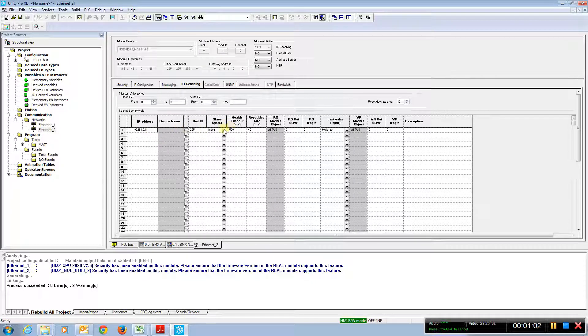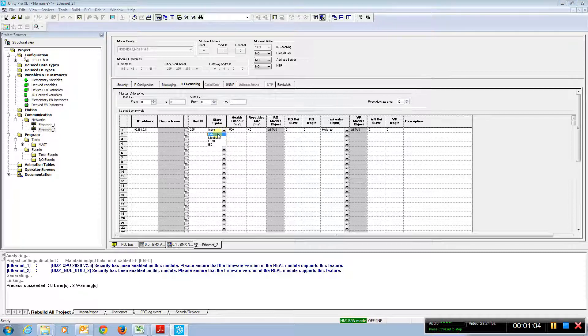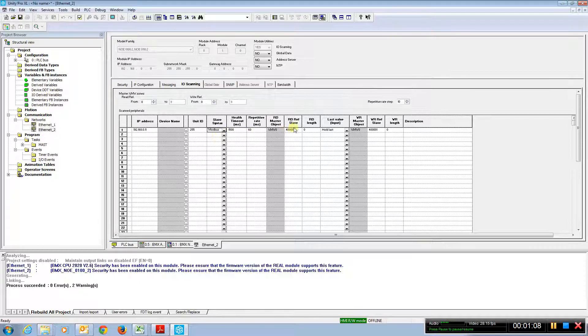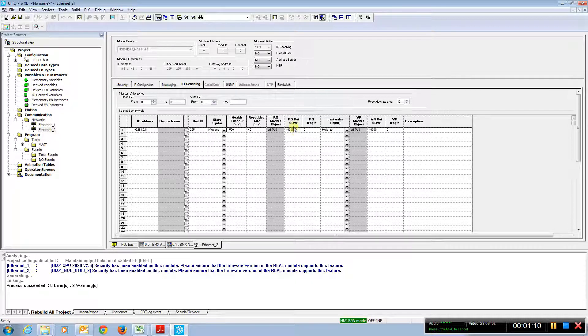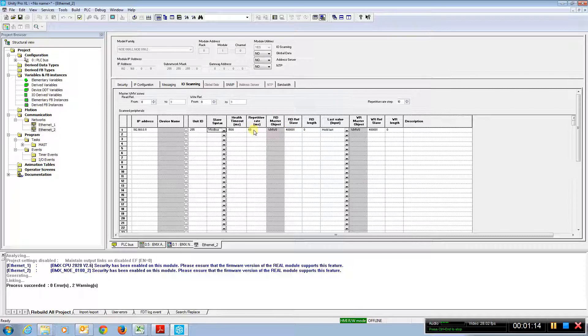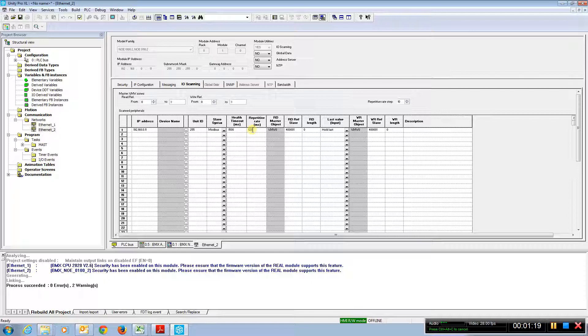We put the slave syntax being Modbus. It changes the slave over here to 40,000 versus just being an index from zero. We can put a rep rate. 60 milliseconds is pretty fast. A lot of times we can come in here and just bump it down to 120 milliseconds.